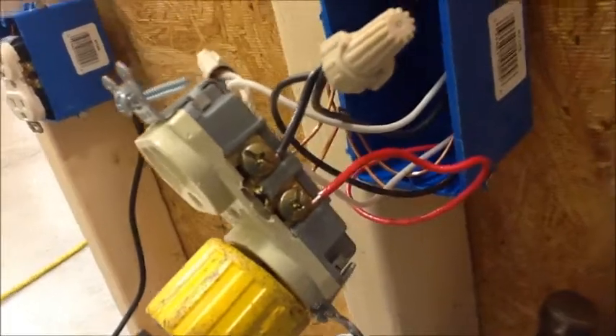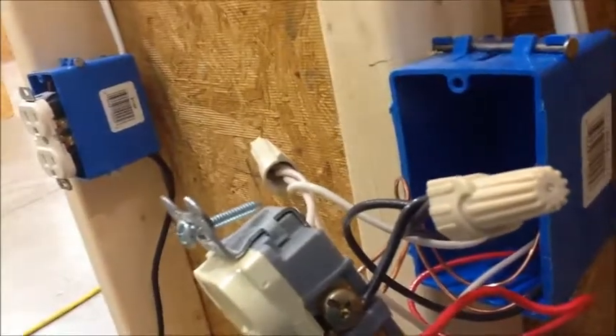Now, it is also possible that you have two wires, like a split wire receptacle, but neither one of them are switched and they're both always hot. In this situation, you would have what is called a multi-wire branch circuit, which basically means this top wire is going to go to one circuit breaker, and the bottom wire is going to go to a separate circuit breaker.